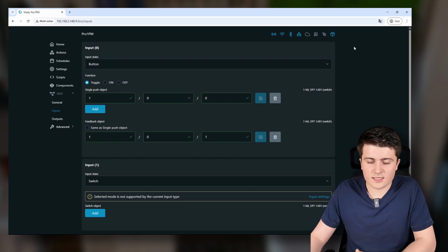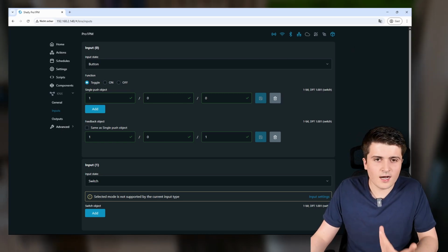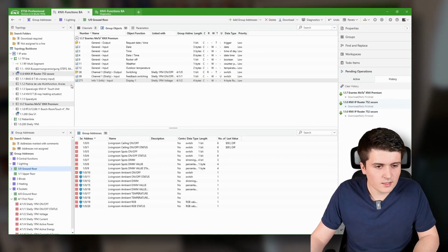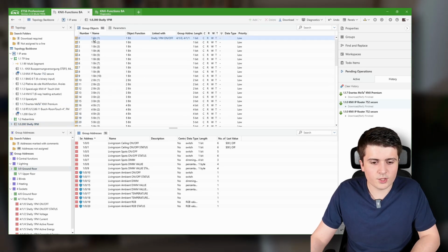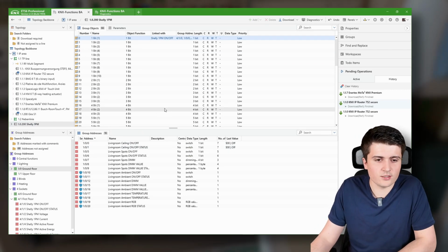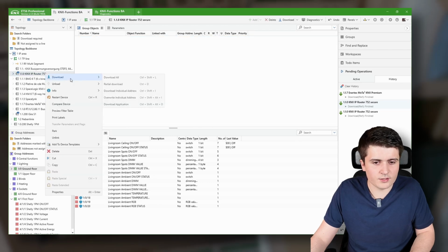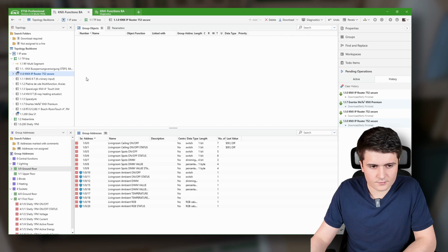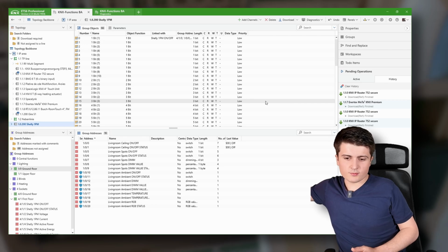And with that being set up, you maybe have already guessed it, we need to connect our dummy Shelly device in the ETS to the corresponding group addresses. So in here I'll go ahead into my Shelly device and simply again use a 1-bit object, connect it to the group addresses that I just set up within the Shelly configuration, and then I can download the KNX IP router. So with that being set up, I can go ahead and press the push button.